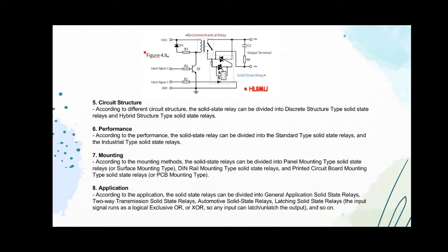According to the application, solid-state relays can be divided into general application solid-state relays, two-way transmission solid-state relays, automotive solid-state relays, and latching solid-state relays. The input signal runs as a logical exclusive OR, or XOR, so any input can latch or unlatch the output, and so on. The latching relay can keep conducting and continuously output the control signal even if the control current is cut off, and it can only be turned off by inputting the reverse current or pressing the off button. So the latching relay is usually used in high voltage circuits to avoid the expansion of an accident.